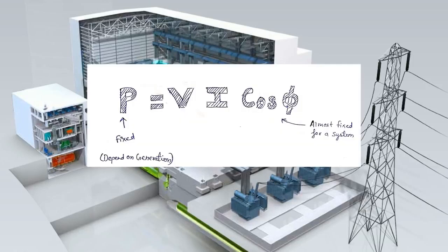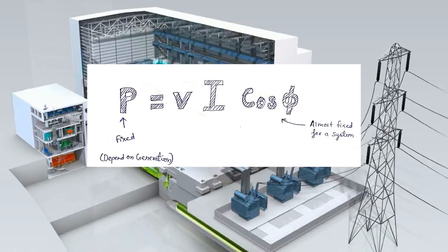So it is important that voltage must be increased to reduce the current so that heat losses are also reduced. Some viewers might be thinking: how can current decrease by increasing voltage? As per Ohm's law, current must also increase with voltage. Dear viewers, don't get confused — in this case electrical power is constant. As we know, the relation is: Power = V × I × cos φ. Taking power factor as constant, it is in our hands whether we want to send power with the combination of higher voltage and low current, or low voltage and high current.